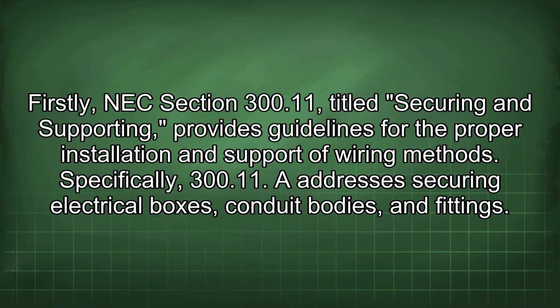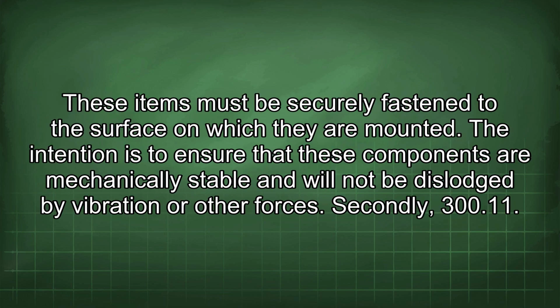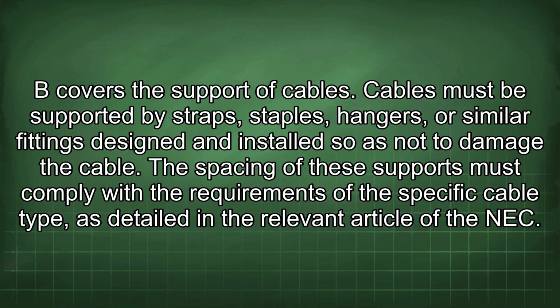Firstly, NEC Section 300.11, titled Securing and Supporting, provides guidelines for the proper installation and support of wiring methods. Specifically, 300.11 A addresses securing electrical boxes, conduit bodies, and fittings. These items must be securely fastened to the surface on which they are mounted. The intention is to ensure that these components are mechanically stable and will not be dislodged by vibration or other forces. Secondly, 300.11 B covers the support of cables.